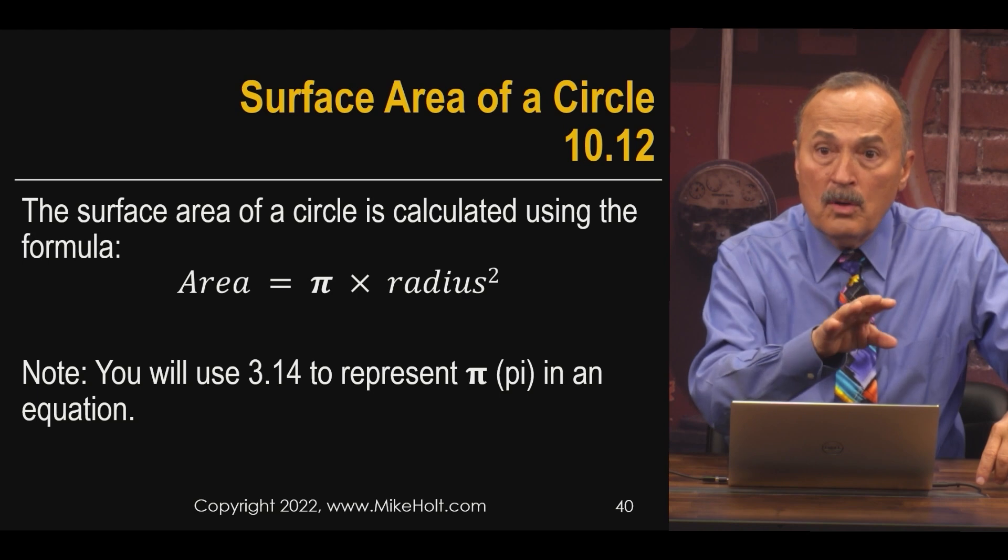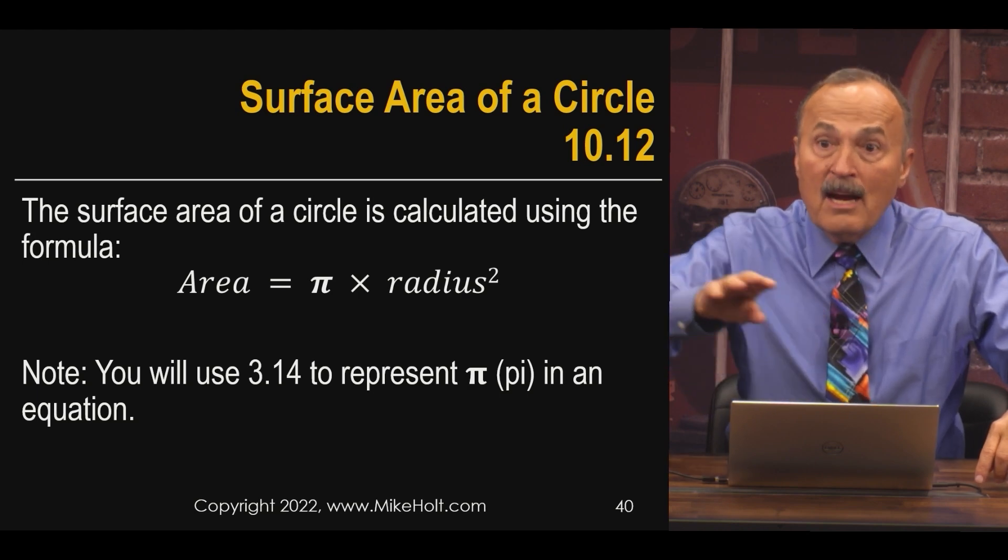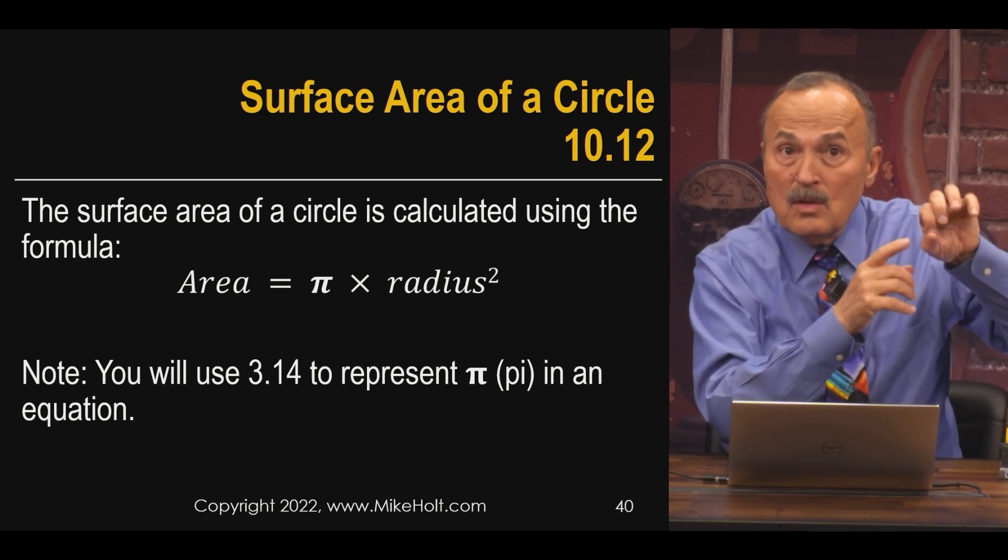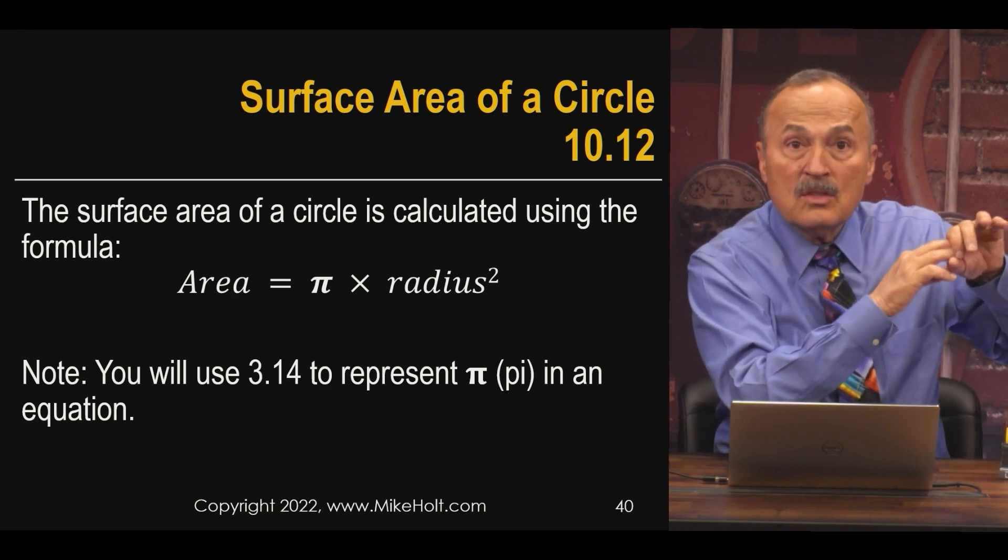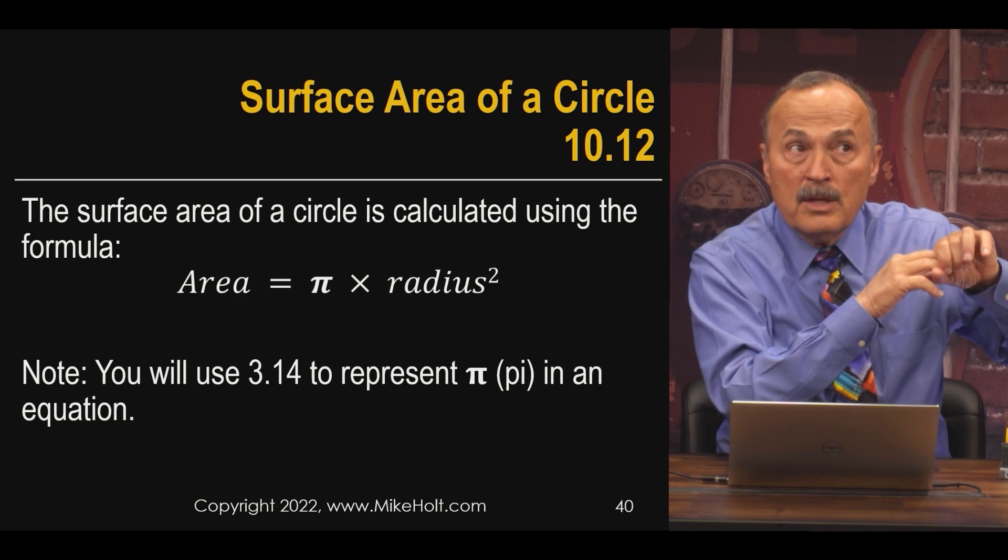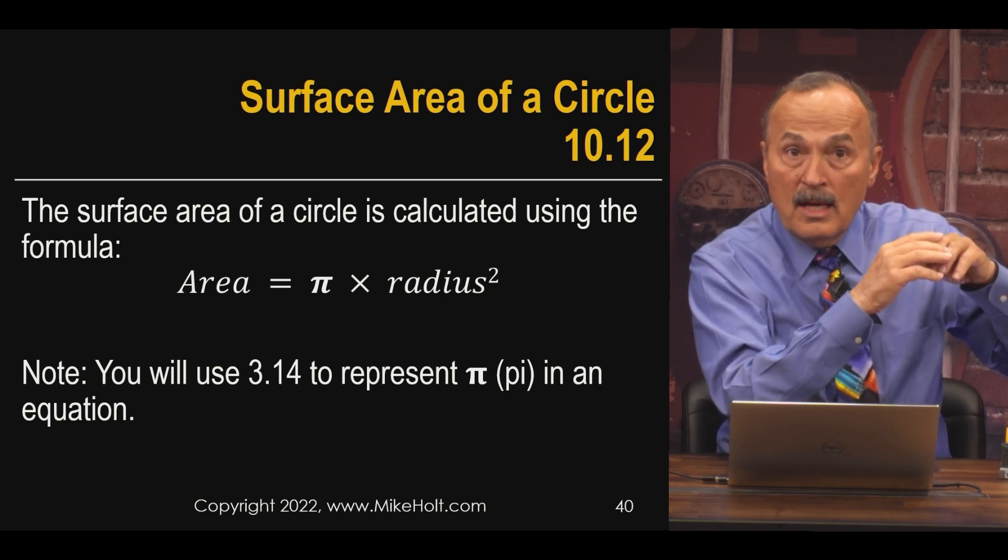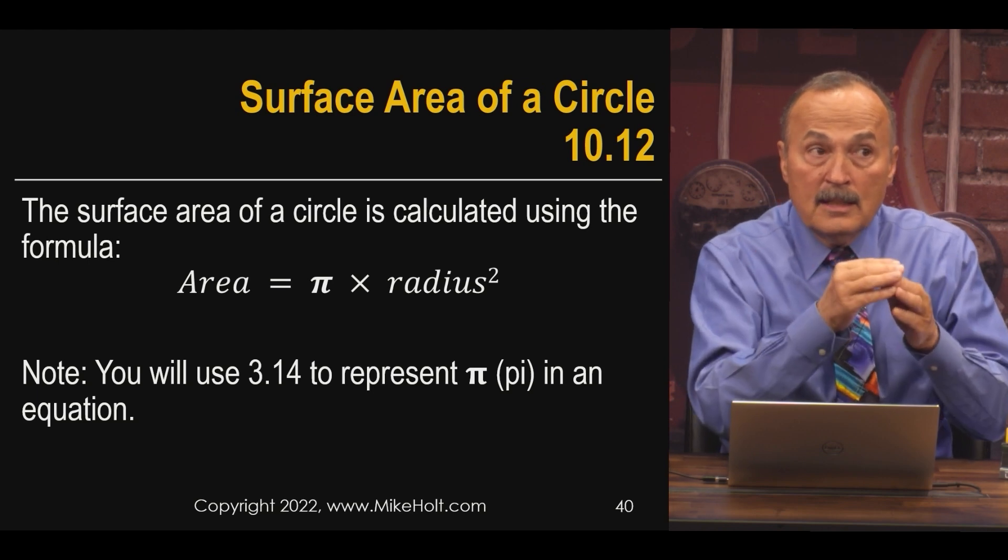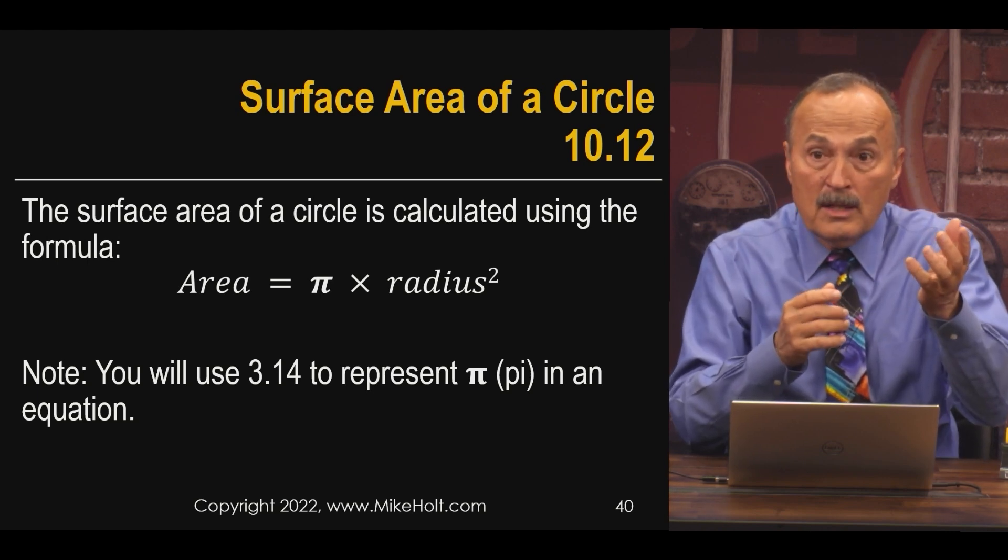The code says, look, if you get wires that are not in this code book, you're going to have to figure out what the area is to do the calculation, because you can only fit so many wires physically inside of a raceway. You need to know the area of the raceway, the allowable fill, and the area of the conductors.